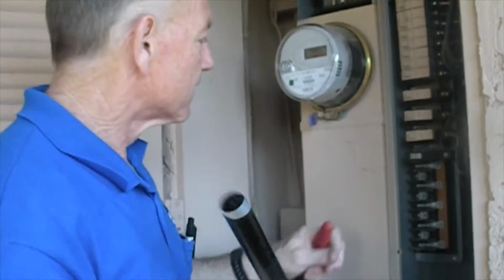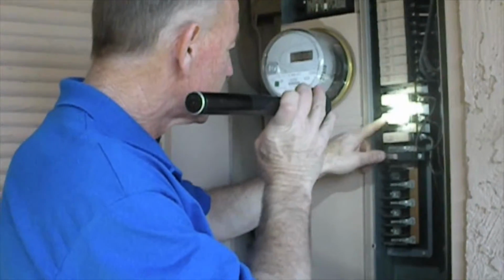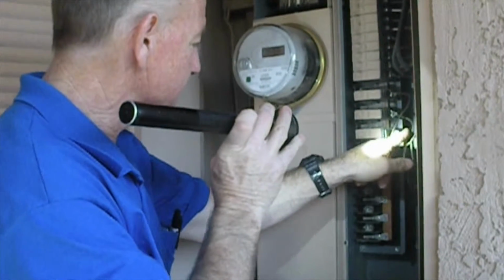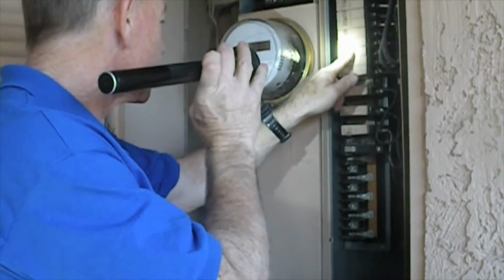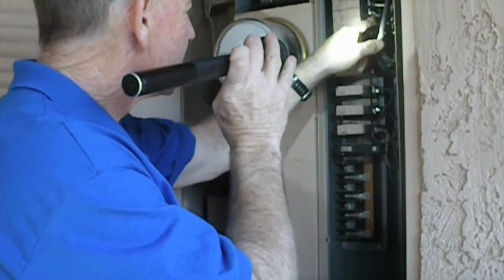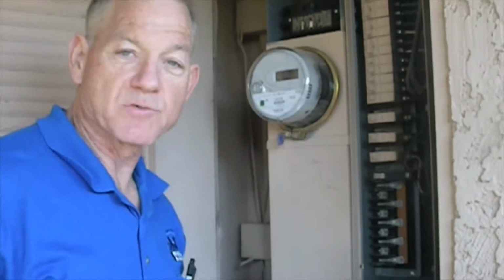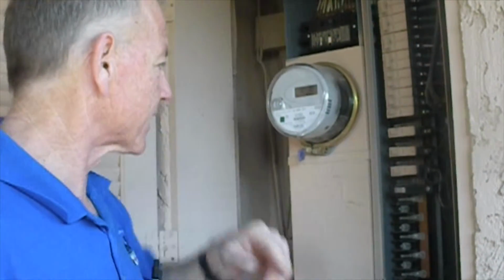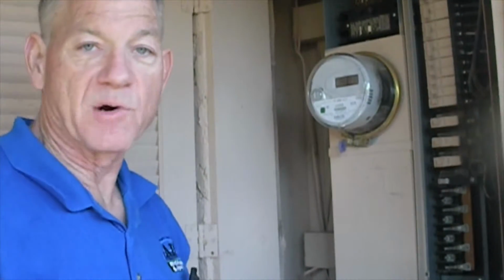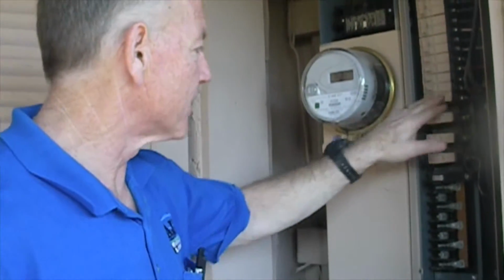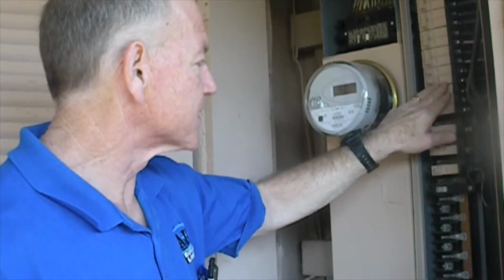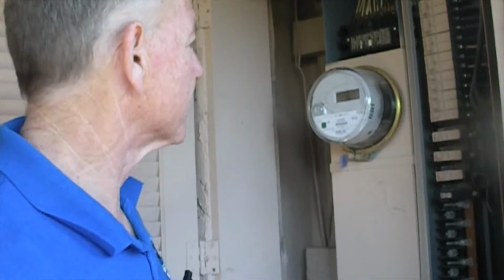These are 15 amp breakers, which should have a certain wire size associated with them. These here are 20 amp breakers, which should have a 12 gauge wire, since they require a thicker wire. Basically, the breaker is designed to protect the wire from overheating, so a certain size breaker needs a certain size wire to go with it. That's one of the things we look at.